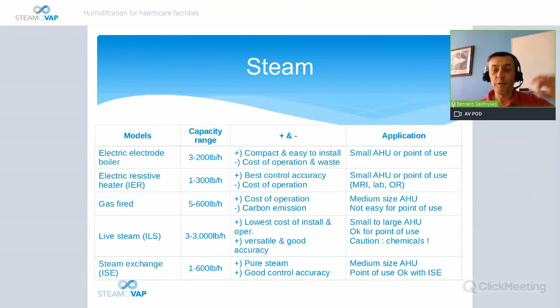Then the live steam. Live steam is widely used in hospitals and large healthcare facilities. Why? Because most of the time they have plant steam, and ASHRAE authorizes the use of FDA-approved chemicals in plant steam, so they can still use it. The other reason, as I mentioned in the previous webinar, is that it's coming back because of the use of unfired steam generators, a dedicated boiler used for the clean steam application in the hospital or healthcare facility.